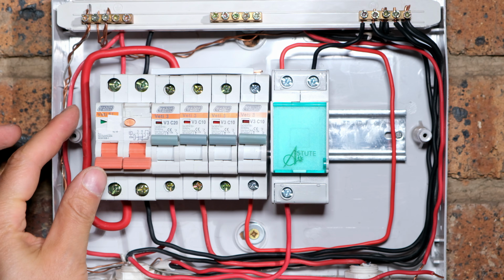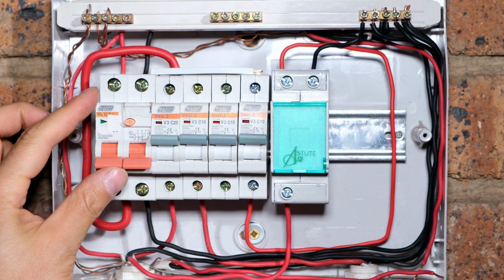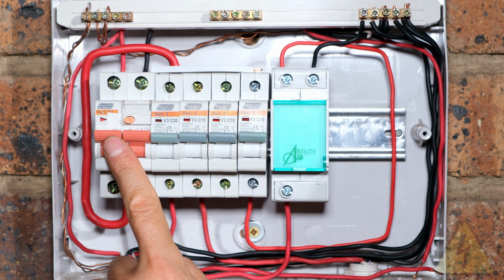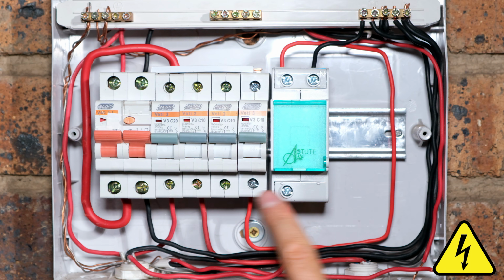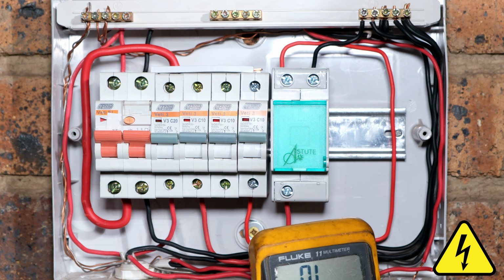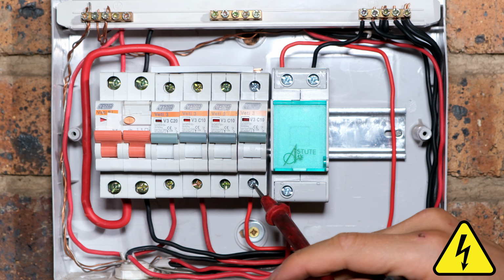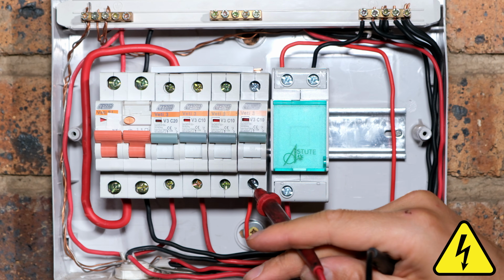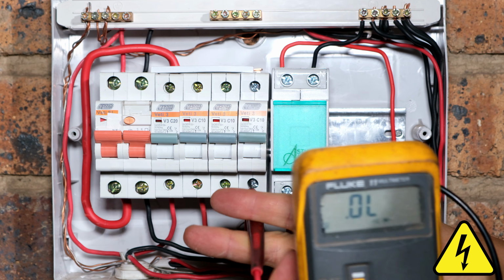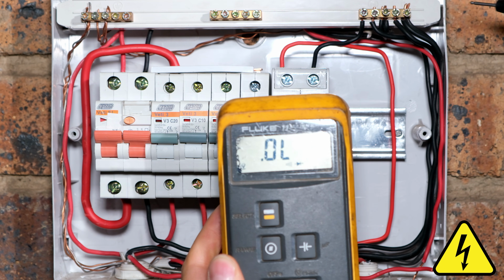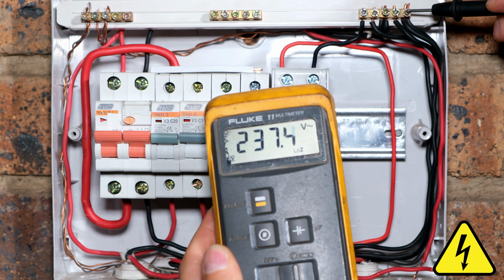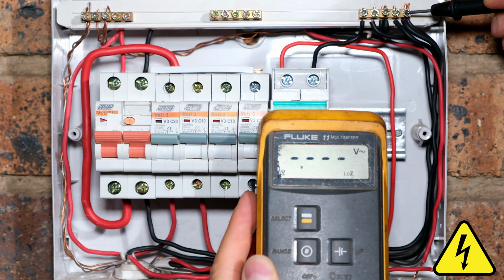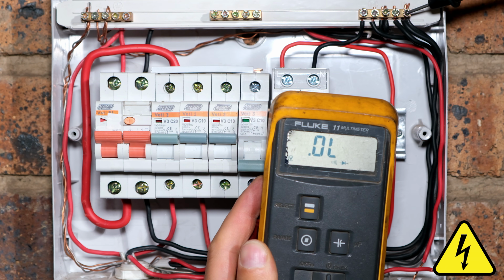So be very careful here, because remember that is still live at the top there. Right, this is up now and this is up. Please be very careful. The board is now energized. I want to quickly check if the output of my circuit breaker here has power. So I'm going to put my positive lead there, and I'm going to put the other lead on the neutral rail. Notice it is 237 volts. If I drop the circuit breaker, nothing.